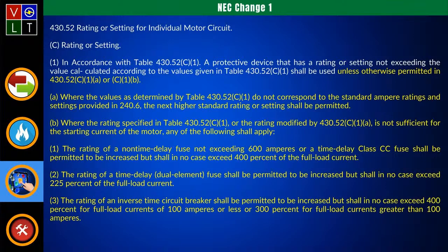Now, something I want to point out for people watching this, we'll look over in a minute and you're going to see table 430.52(C)(1). It's going to say maximum. That's the maximum for that table. It's not the maximum overall. And what I like to point out here is in our design book, Journeyman, Masters, all of them that we have, we go in and discuss this. We start this as our minimum point, even though the table says maximum. And then we would go to the exception, and then exception number 1. Well, now it's 430.52(C)(1)(a), and it basically says without doing any further calculation, if the motor won't start to the inrush current, then I'm automatically allowed to go up to the next standard size.